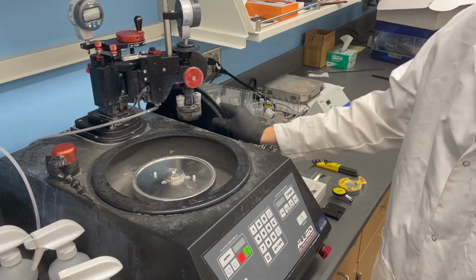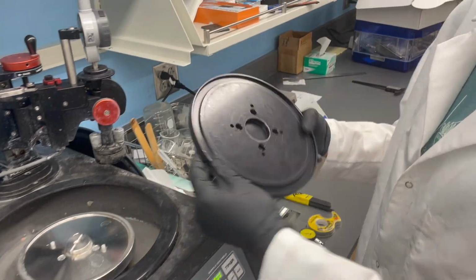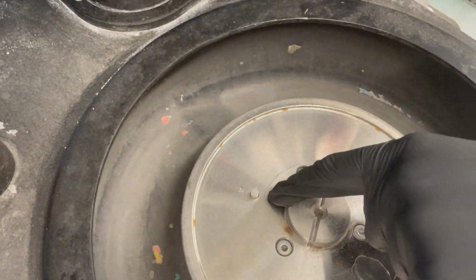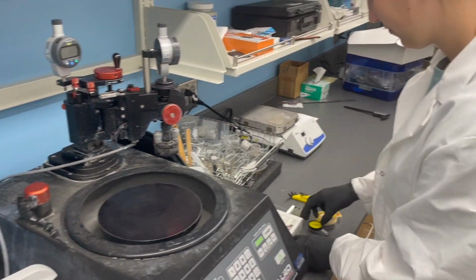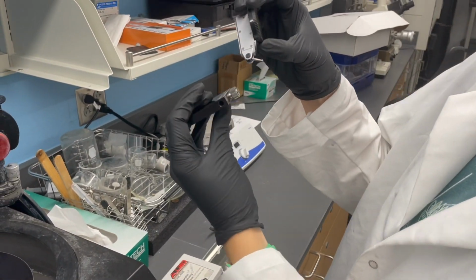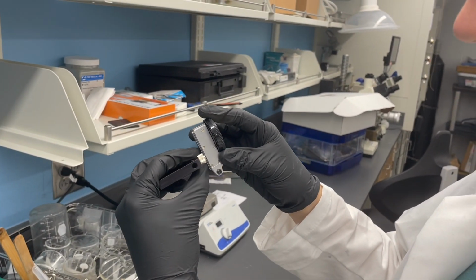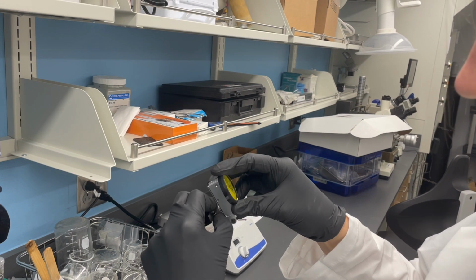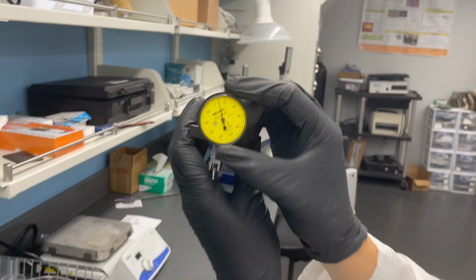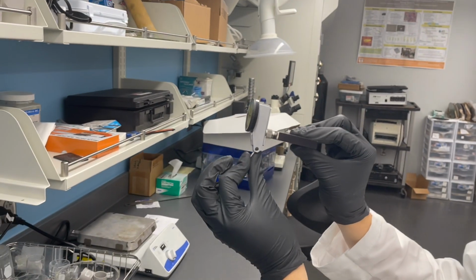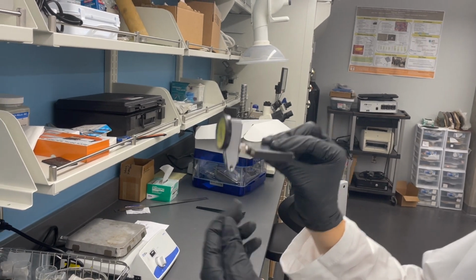To begin calibration, remove the lid and turn the polisher on. Align the hole marked with an A to the peg marked with an A. Take the dial and attach it to the calibration tool. Ensure the top side is facing up. Align the tool about 1/3 of the way from the bottom. Ensure the needle is at 0 and adjust the arm to 45 degrees backwards.